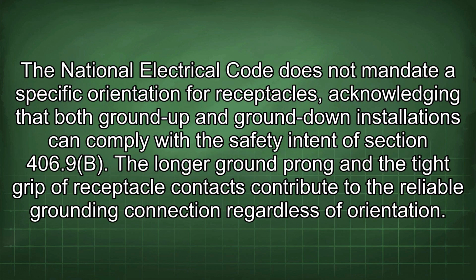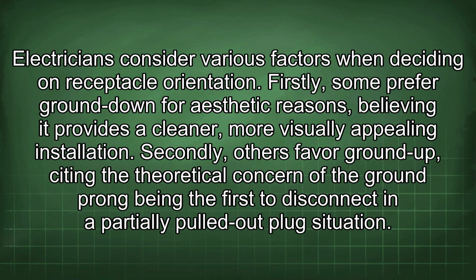The National Electrical Code does not mandate a specific orientation for receptacles, acknowledging that both ground-up and ground-down installations can comply with the safety intent of Section 406.9b. The longer ground prong and the tight grip of receptacle contacts contribute to the reliable grounding connection regardless of orientation. Electricians consider various factors when deciding on receptacle orientation. Firstly, some prefer ground down for aesthetic reasons, believing it provides a cleaner, more visually appealing installation.